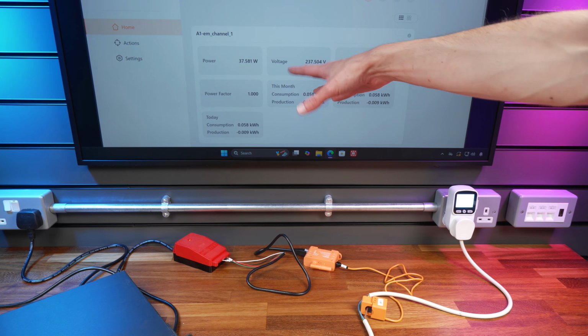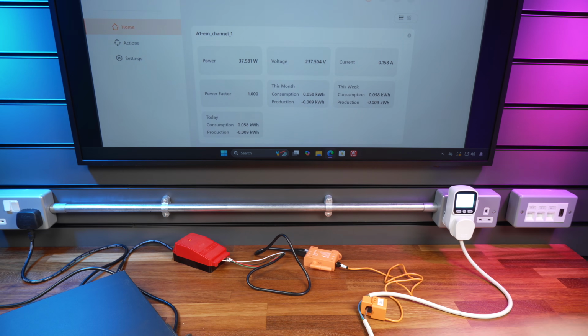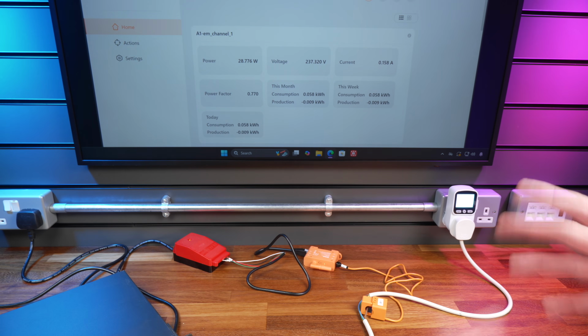So as you can see there, it was reading the correct power factor, and now it's jumped back up to 1 again. So there's something really weird going on here with how it's measuring the power factor, and it's not keeping a consistent value. And I've tested this with a bunch of different devices, a bunch of different sensors into different ports on the CT, all that sort of stuff.